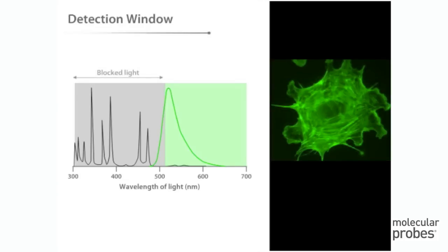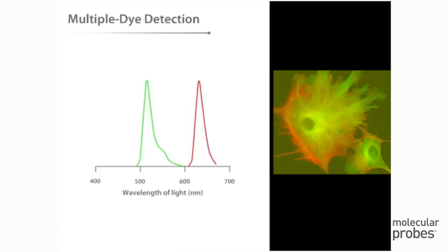When a single dye is used, a filter that blocks out the excitation light to reduce background noise but transmits everything else is often a good choice to maximize the signal collected. Such a filter is called a long-pass emission filter. If multiple dyes are used in the sample, a band-pass emission filter can be used to isolate the emission from each dye.